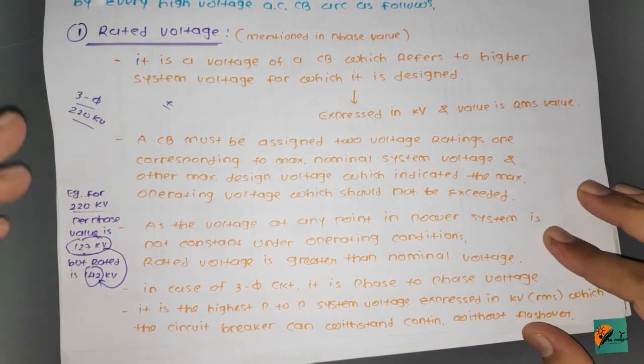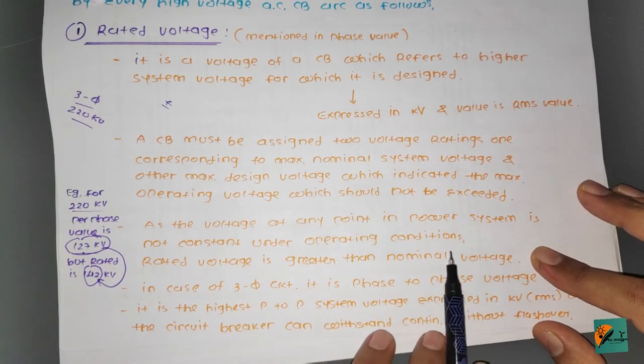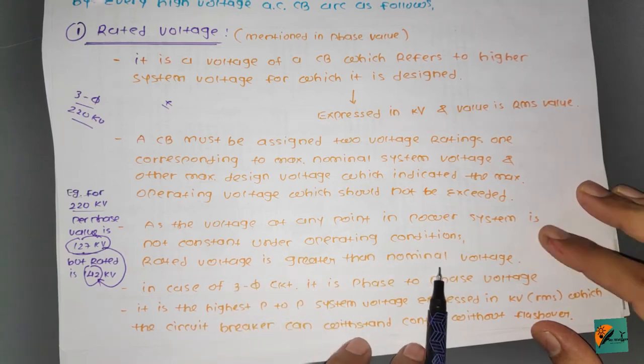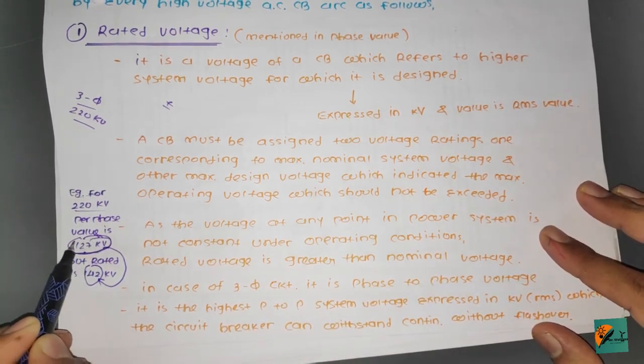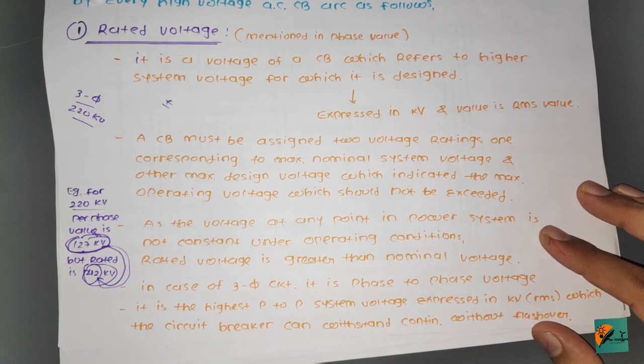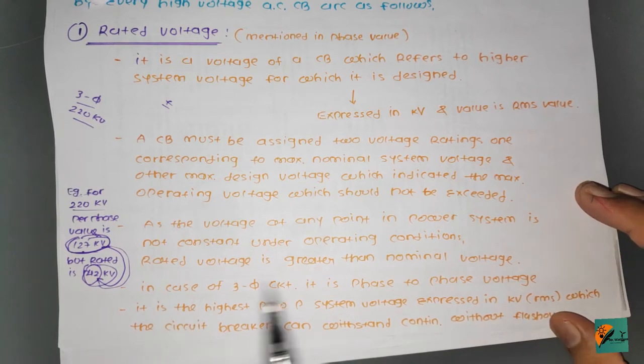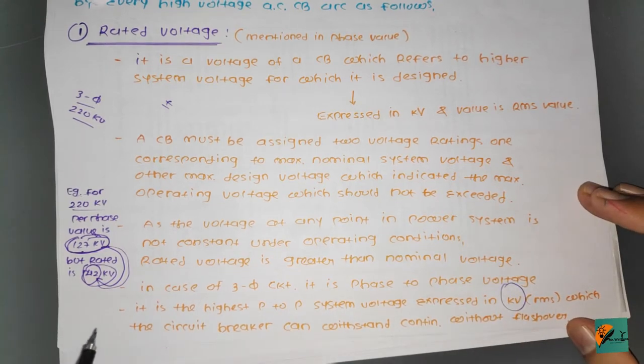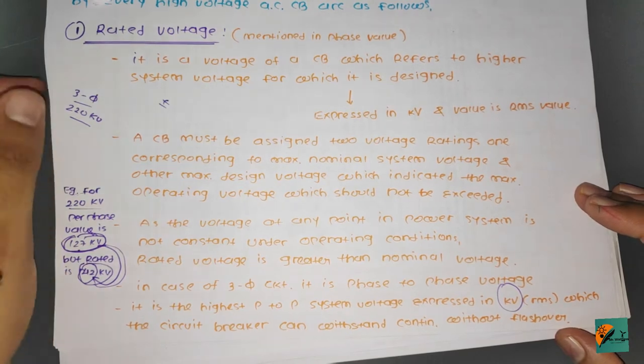Since the voltage at any point in a power system is not constant under operating conditions, the rated voltage is greater than the nominal voltage. In the case of a three-phase circuit, it is the phase-to-phase voltage — the highest phase-to-phase system voltage expressed in RMS kilovolts that the circuit breaker can withstand continuously without flashover or any failure.